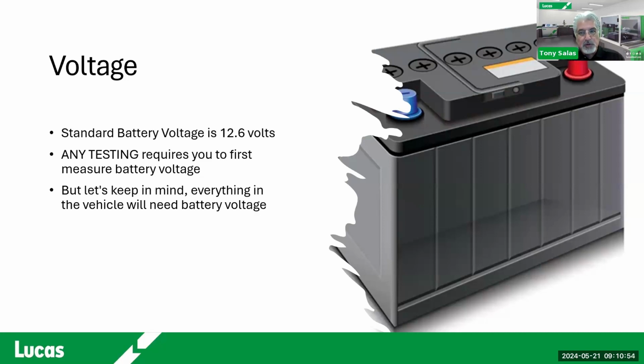Now some people will argue and say, wait a minute Tony, the lift pump has 12 volts. Yeah, but it doesn't have battery voltage now, does it? So in this case, anytime you do voltage drop testing, you need to reference first what is your source power and how much is your source power. So any testing, like the slide says, requires you to first measure that battery voltage.